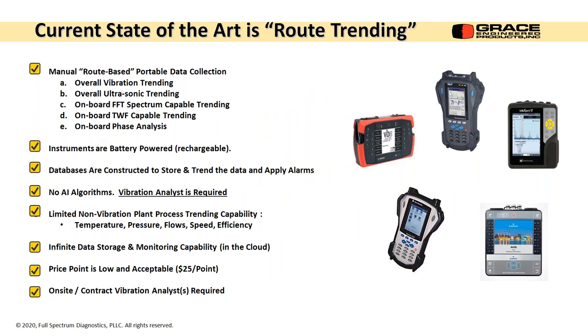Current state of the art is route trending. And why do we stop that? There's a lot of inaccessible locations. There's dangerous things that you can't monitor as well as you'd like to. That is perfect for permanently mounted battery-powered units, especially at a lot of places I go, like refineries. You just don't want to be close to some of these machines. What they have out in the market right now, battery-powered units, they do everything. They do the trending, the ultrasonic, the spectrum, the waveform, phase analysis, orbits. They can do all kinds of natural frequency tests. Anything you think of, they're thrown into these portable units. It's just, you have to have a skilled guy that knows vibration and knows how to use it and get the most out of it.